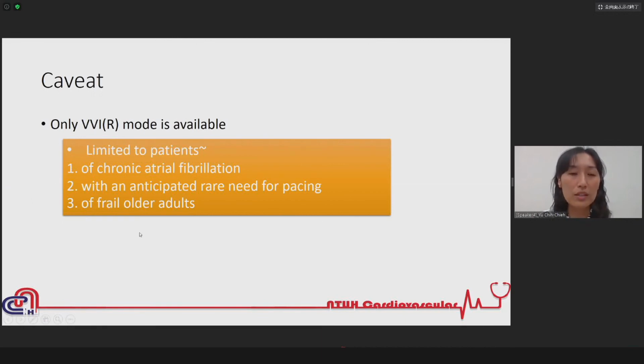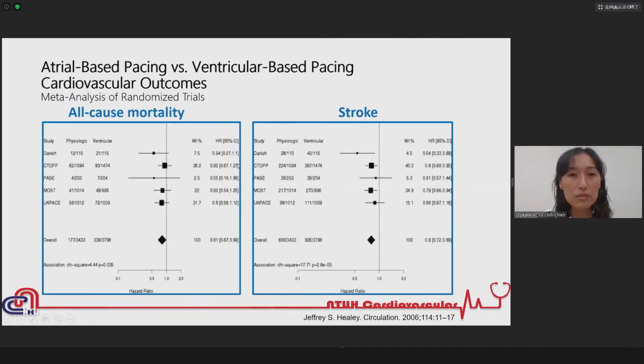But when considering implanting this device, we still need to know that only VVIR mode is available. Therefore the device is limited to patients with chronic atrial fibrillation with rare need for pacing, or very frail older adults. Looking back at meta-analyses comparing atrial-based versus ventricular-based pacing, ventricular-based pacing like MICRA's VVI mode has higher all-cause mortality and stroke rate than atrial-based pacing. That's what we should pay attention to.